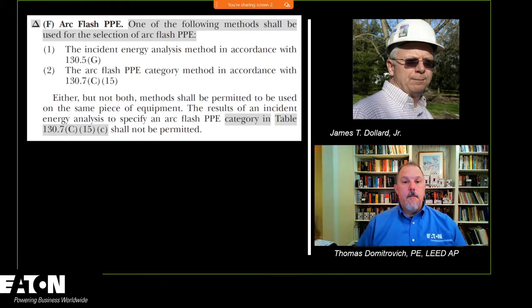Either but not both methods shall be permitted to be used on the same piece of equipment. This last sentence is extremely important. The results of an incident energy analysis to specify an arc flash PPE category in table 130.7(C)(15)(c) shall not be permitted. Yep. And there's good reason for that.